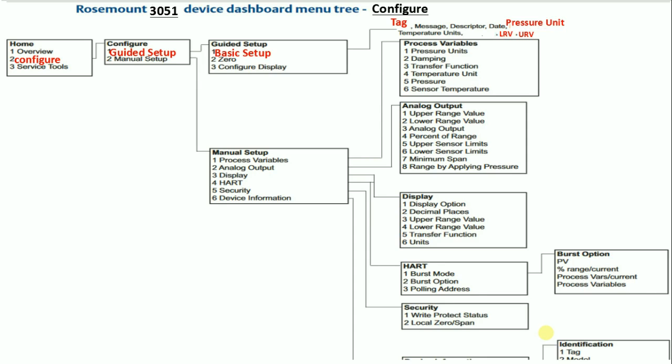Set the damping also according to your range. This is the basic configuration for pressure or differential pressure transmitter to be done before calibrating.